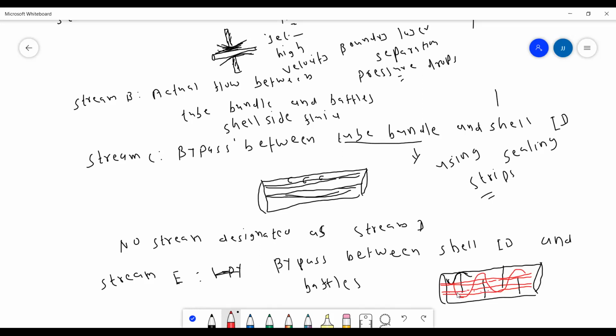This is the real flow, but due to some gap between shell ID and baffles, some of the shell side fluid directly bypasses through this gap. So this fluid cannot come into contact with the tubes, it will not transfer heat, and it actually reduces the shell side heat transfer coefficient.